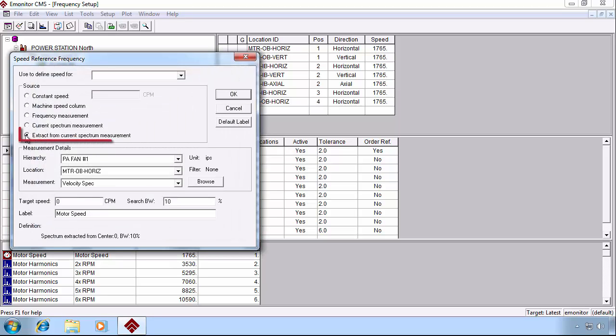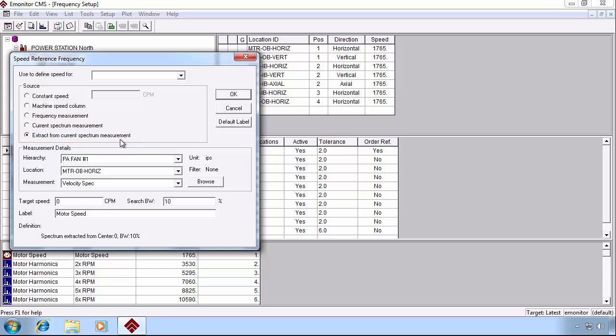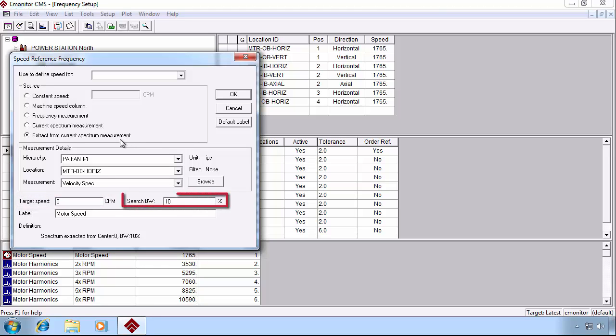Alternatively, if we're not getting speed with the spectrum measurement, we can extract it from the current spectrum measurement. And what it does in this case is we provide a target speed range where we expect the speed to be approximately, and a search bandwidth percentage on either side of that peak.